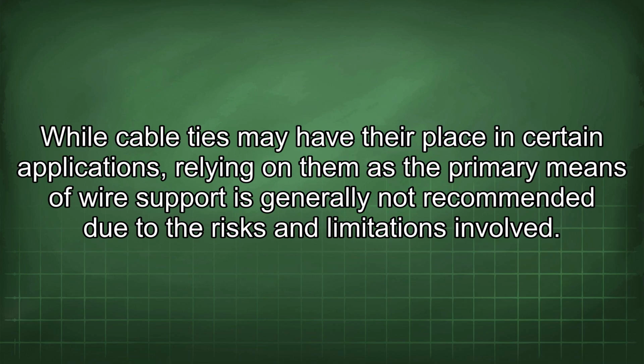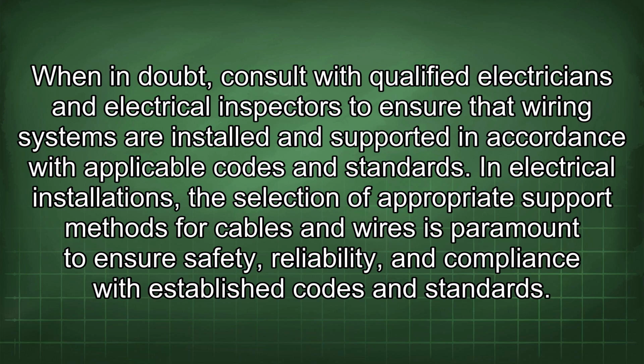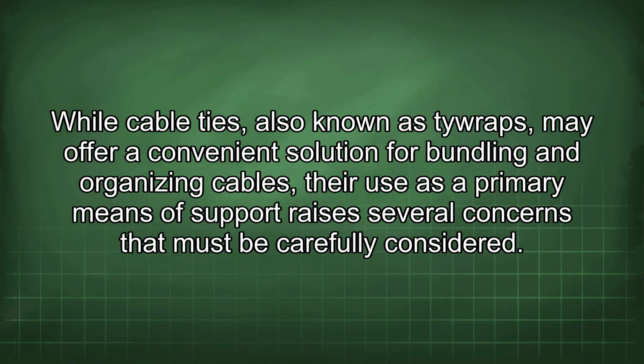While cable ties may have their place in certain applications, relying on them as the primary means of wire support is generally not recommended due to the risks and limitations involved. When in doubt, consult with qualified electricians and electrical inspectors to ensure that wiring systems are installed and supported in accordance with applicable codes and standards. In electrical installations, the selection of appropriate support methods for cables and wires is paramount to ensure safety, reliability, and compliance with established codes and standards. While cable ties, also known as Tywraps, may offer a convenient solution for bundling and organizing cables, their use as a primary means of support raises several concerns that must be carefully considered.